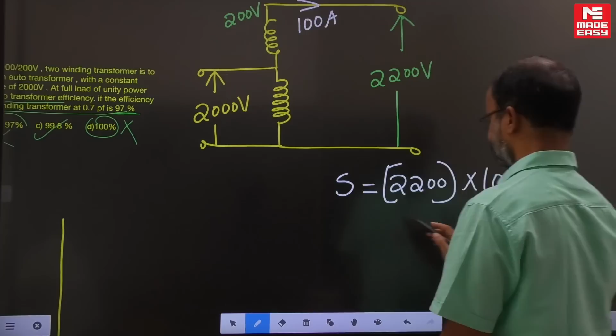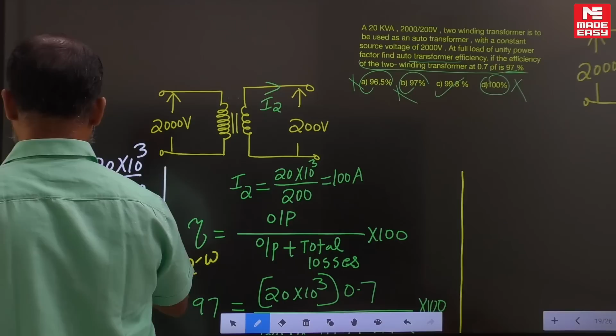Now in this example, what is I1 equal to? The kVA rating is 20 kVA. 20 kVA divided by 2000, if you simplify this, I1 equals 10 amperes. This indicates the same current in this winding.